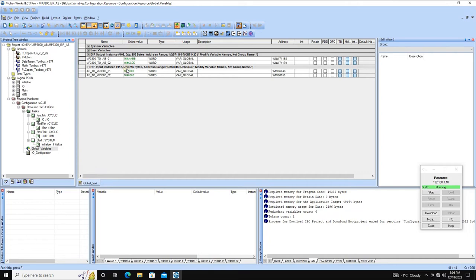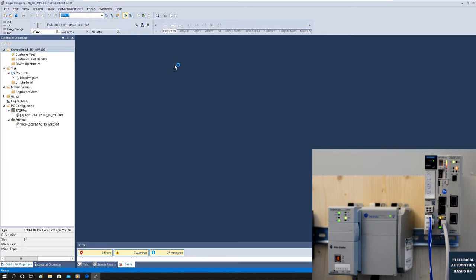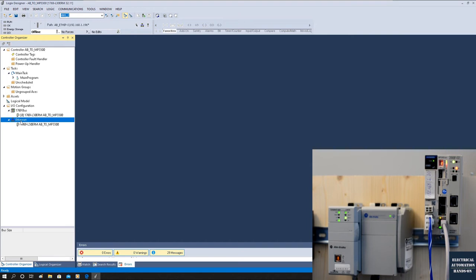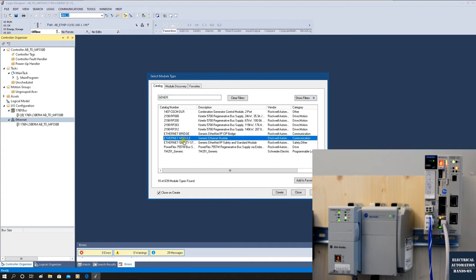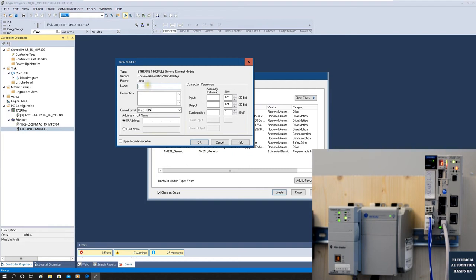Now let's shift to the Allen-Bradley side. This is my Allen-Bradley system and I'm using Studio 5000. My controller is a CompactLogix, Version 32 — a very commonly used controller in industry. The controller is an L30 ERM with IP address 192.168.1.196. I'm going to set up the Ethernet IP communication. When setting up this connection, we do not need any EDS file. We set up a generic module and configure the input and output assembly numbers. From the Ethernet tree, click New Module and search for Generic Connection — select Generic Ethernet Module and click Create.